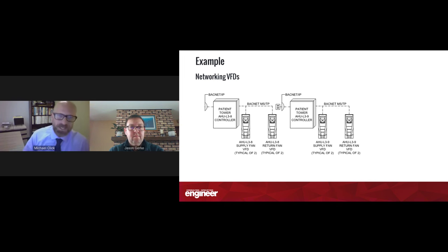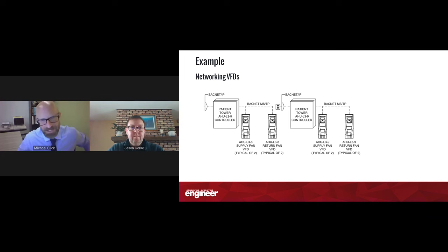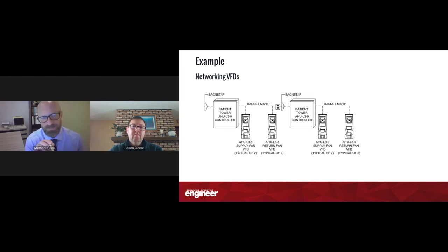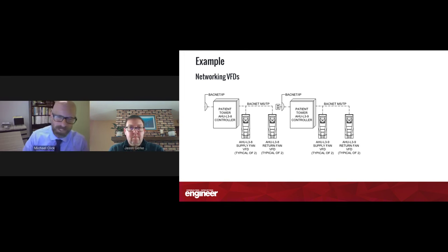A quick example of networking VFDs: many are now IP-related BACnet VFDs and not MSTP. The difference is MSTP is a serial connection RS-485, while IP is through Ethernet. VFDs are controllers, and they're all networked together with your system-level controller. There are controls within those VFDs that we need to pay attention to, making sure those are programmed correctly as far as ramp rates and how things are determined.